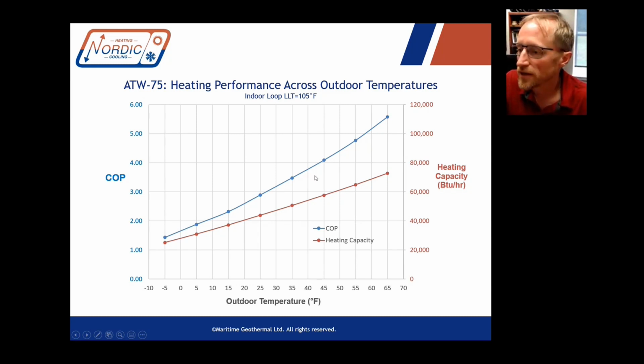So there's a characteristic curve of how that varies, and same with the capacity. So for an ATW 75, which is the largest, the 5-ton model size, you can see at a very warm outdoor temperature, you can have a heating capacity of around 70,000 BTU per hour, which is probably 5.8 tons or something like that. And at the coldest outdoor temperature that the heat pump operates at, you're down to about 26,000 BTU per hour or something like that.